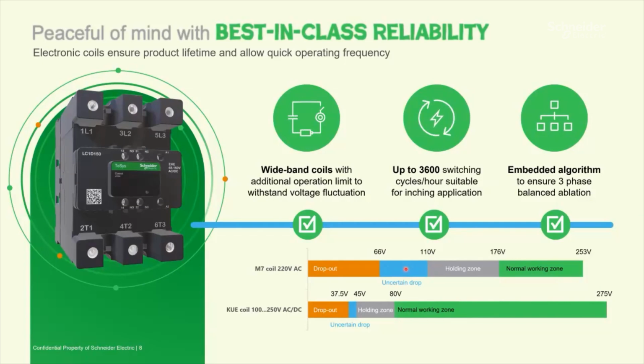And when you are not certain, you see an abnormal cause which we call chattering. There will be continuous on-off operation of the contactor, and when this happens due to low voltage, it consumes electrical life. Eventually, after a few days or few months, you will see that the contactor has failed. So for remote operations, wherever voltages are not proper, you will still have good holding of contacts with the new coil, which is the KUE coil.